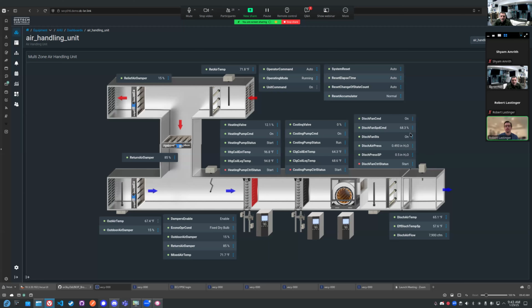For example, if I go to my discharge fan speed, it's at 68% and maintaining pressure, and I override it—let's go to 100. We can watch what happens: the pressure shoots up, as you'd expect in a real air handler. You speed it up, it's going to build pressure in the ductwork.